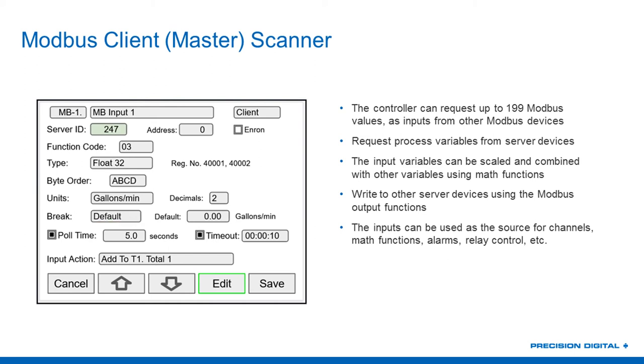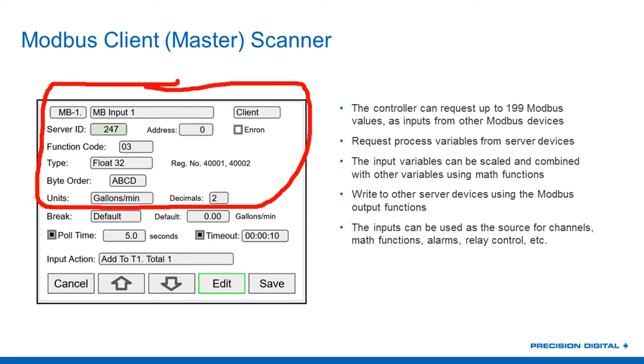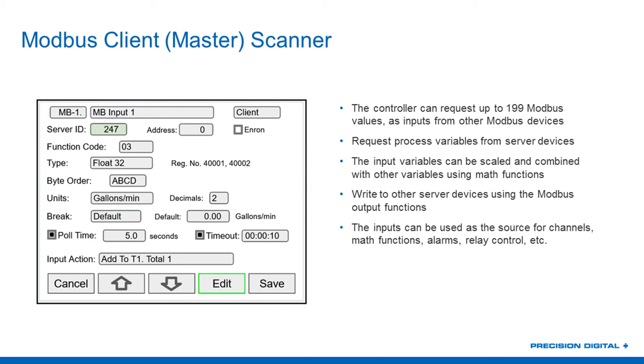Most people are just going to give it a name, connect it to the device, punch in the address, function code, type, and byte order right out of their device manual, and be done. After that, you program it just like any other 4-to-20 milliamp input. Because these are programmed just like any other input, you can use them for math functions, alarms, relay control — really anything you want, including multi-pump alternation based on tank level.